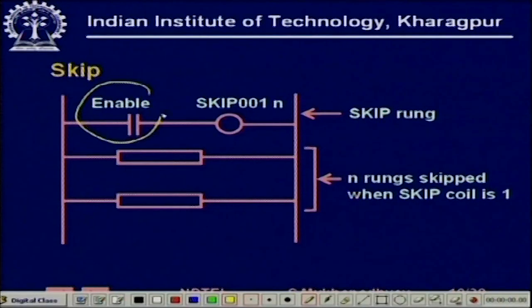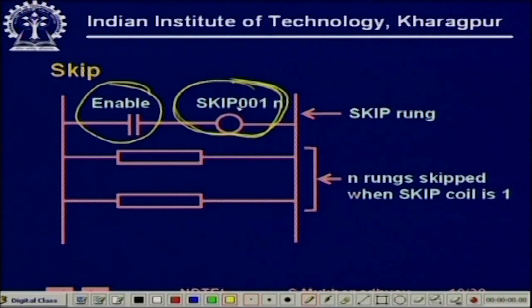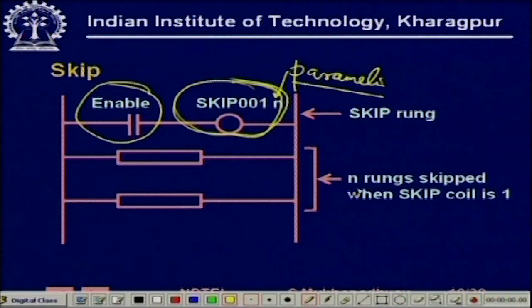Apart from data transfer, very important are program control instructions by which we want to control the execution of rungs — we do not want to execute all rungs of the RLL at all times, but rather skip some or enforce their values. We have a skip facility: when the skip instruction is enabled, the next n rungs will not be evaluated. Skip001 with parameter n means the next n rungs are skipped while this is high.